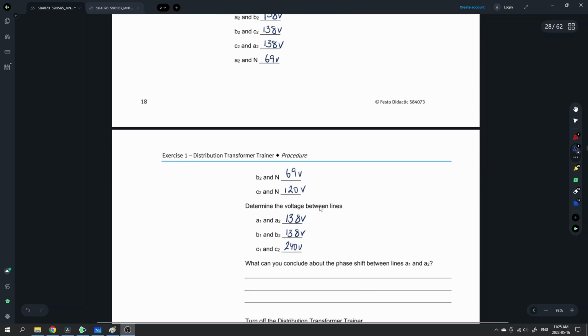Now looking at the voltages between the lines: A1 and A2 we're seeing 138, B1 and B2 we're seeing 138, and then C1 and C2, the C phase is consistently having the higher voltage, being 240, and it seems like it's always root 3 of whatever the A or B voltage is. So if we take 138 volts and multiply by 1.732, that gives us 240 volts between the two C phases.